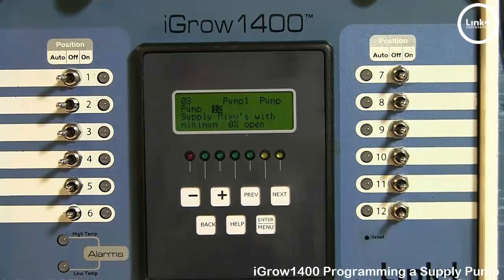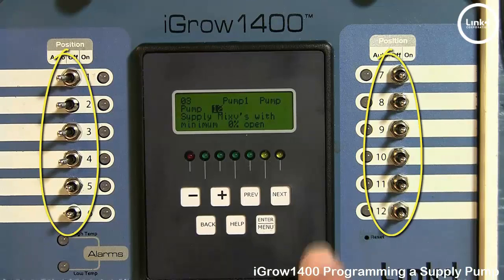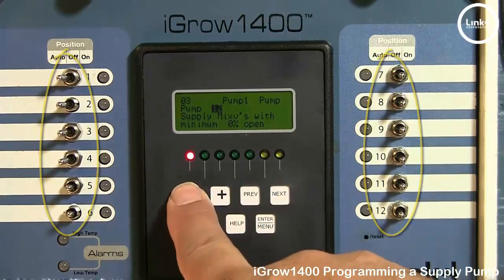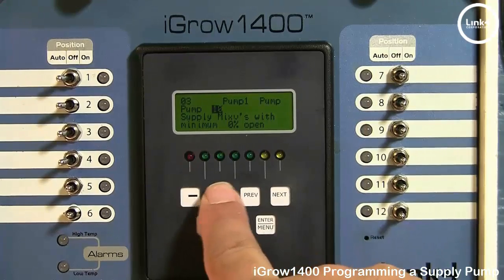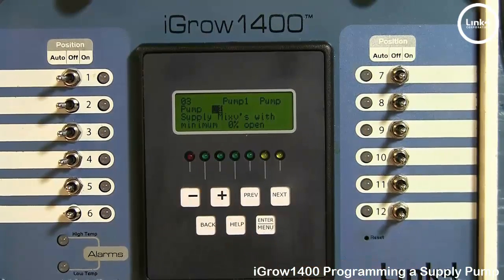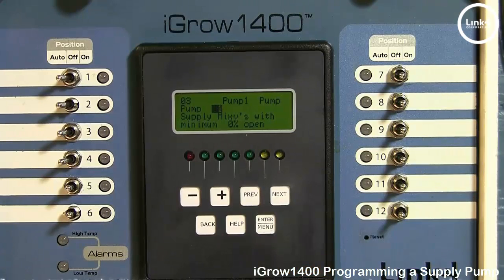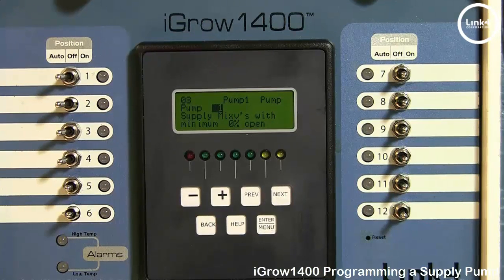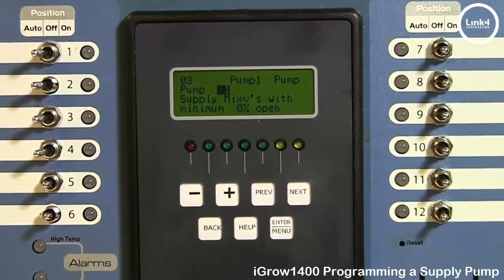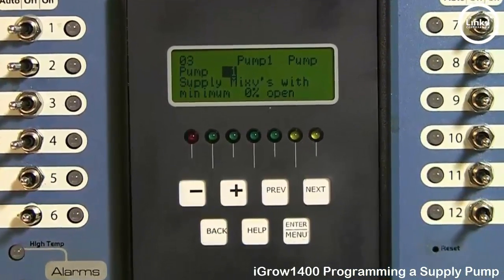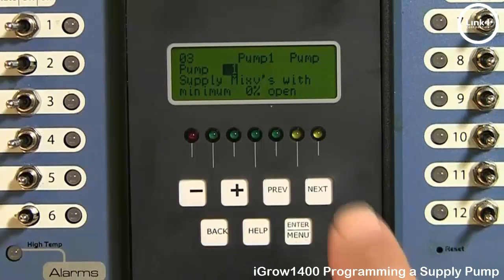Now in the programming, you would first assign the pump a number, an address associated with this pump's output. Now it could be pump 1, pump 2, pump 3, all the way to pump 12, and you would increase and decrease the values by simply hitting plus and minus, but we're going to make this output be pump number 1. Now, if you're using mix valves on this controller, the programming would need this output's address if it's to use this output as its supply pump.